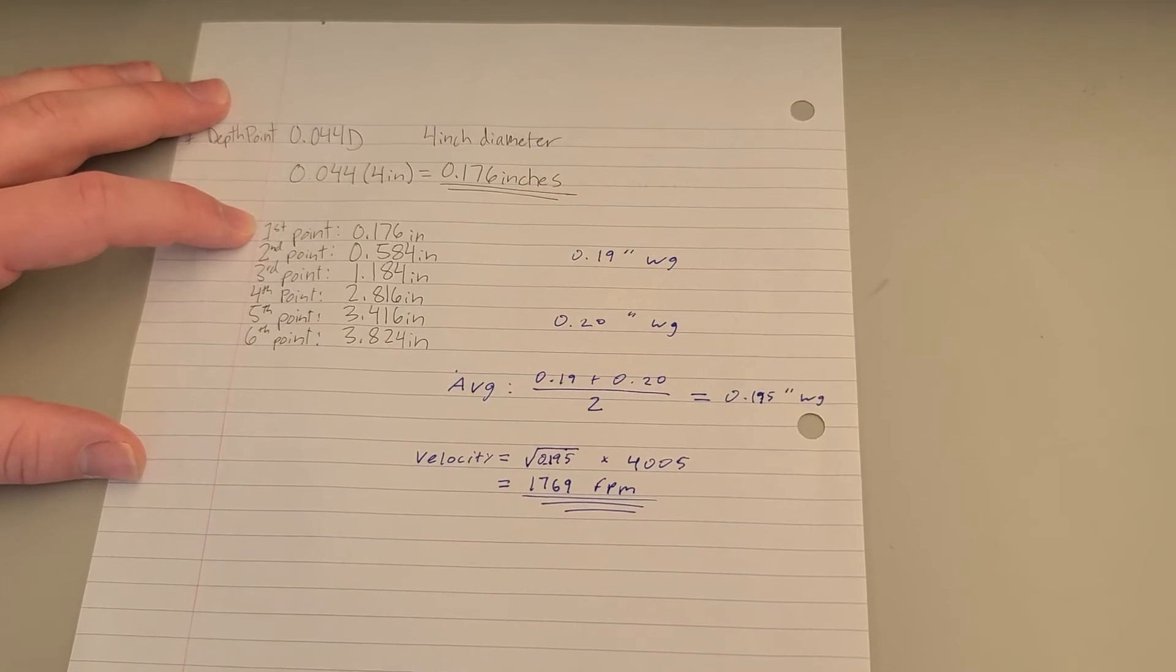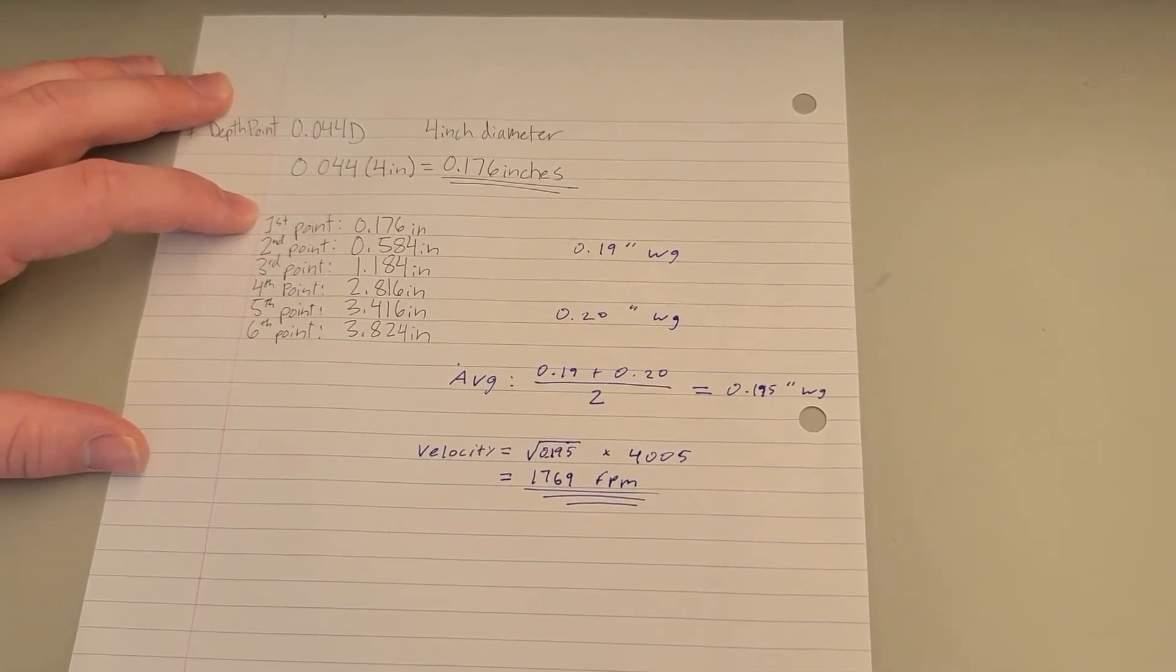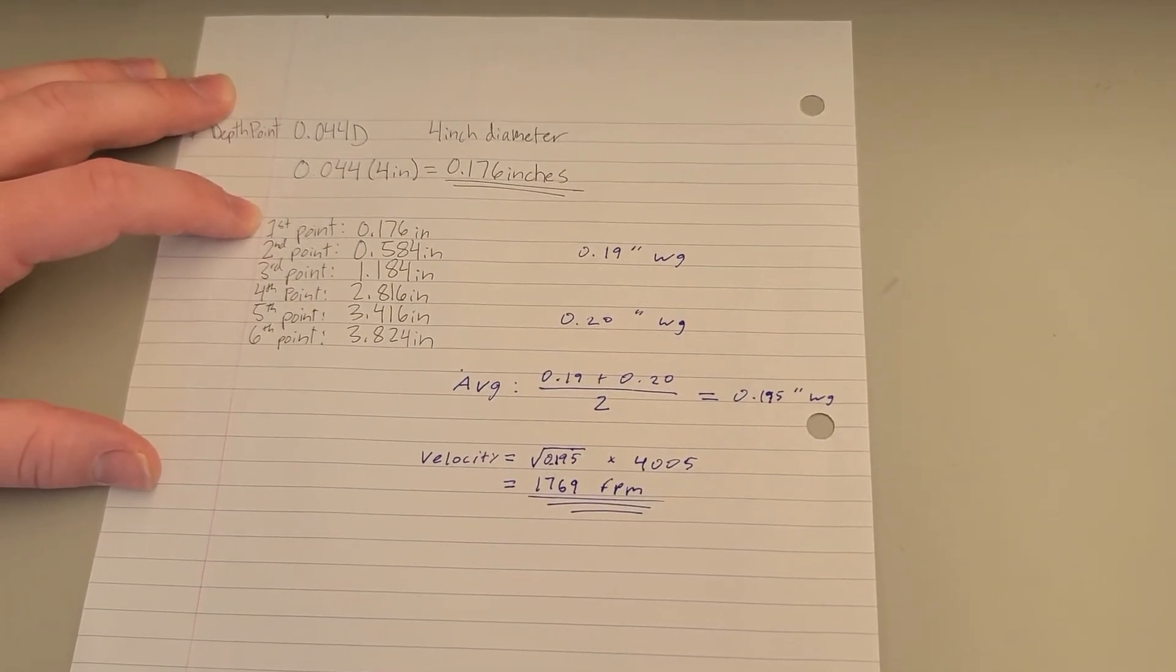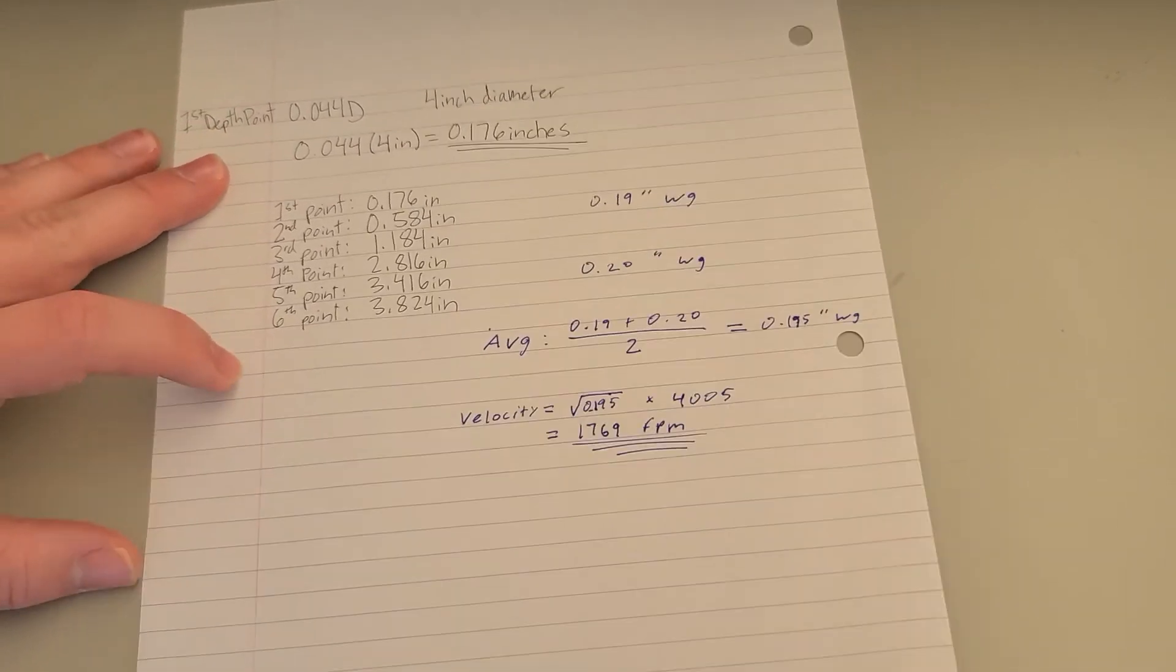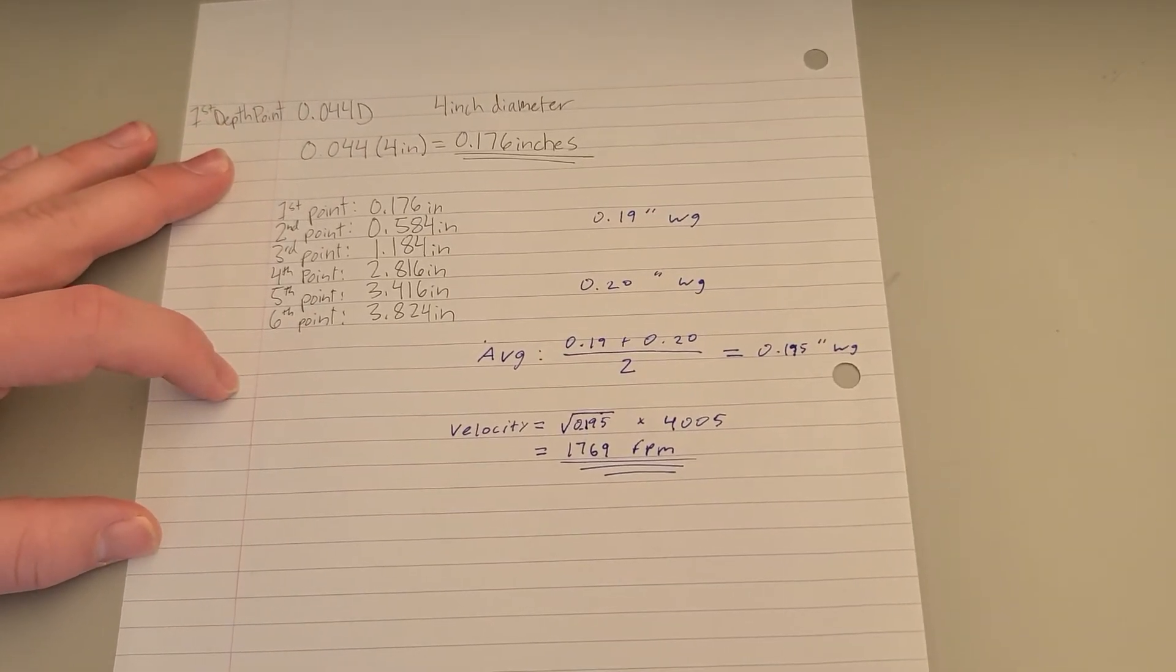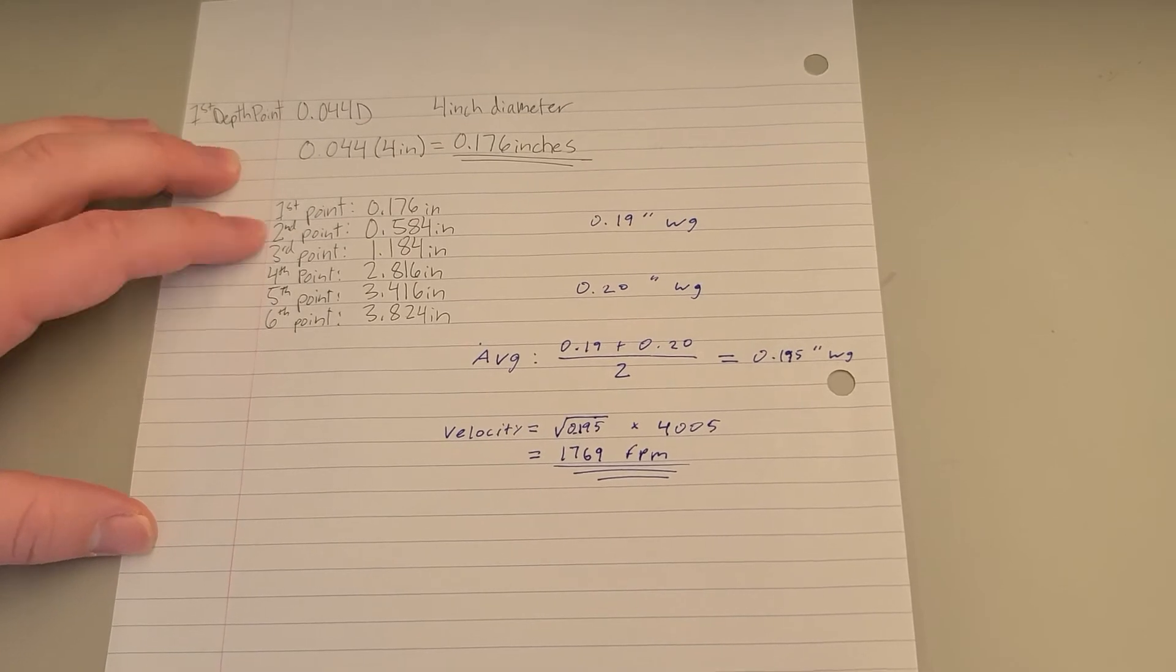Remember that in an actual duct traverse, you would calculate your average from six points of a duct traverse, as well as another six points taken at a 90-degree angle to those original six.